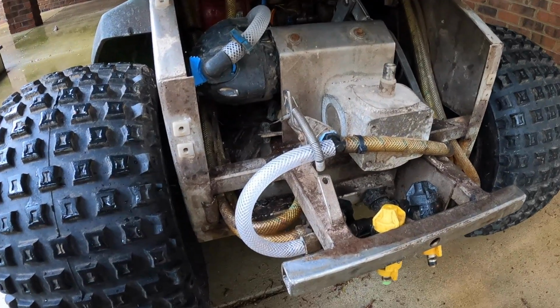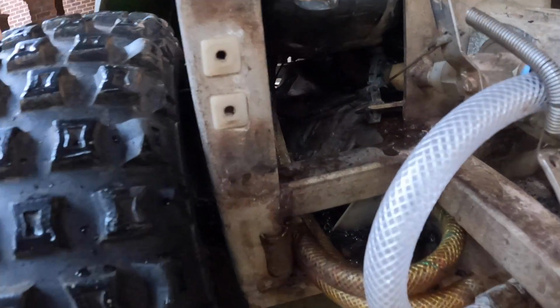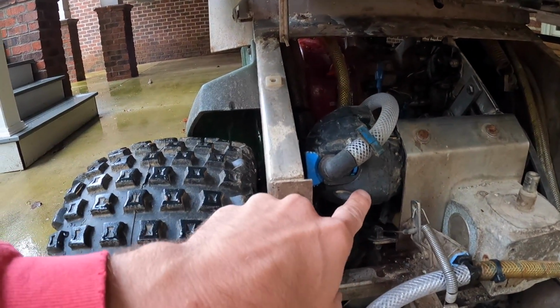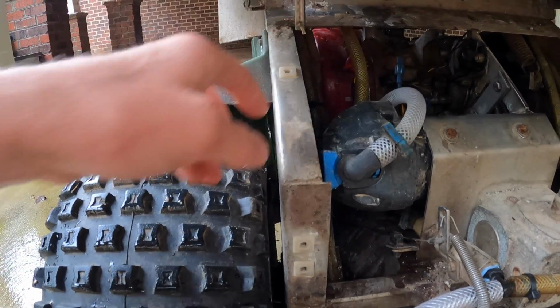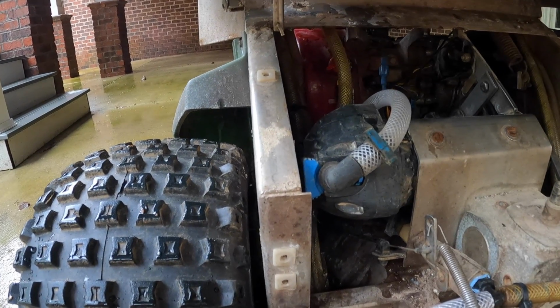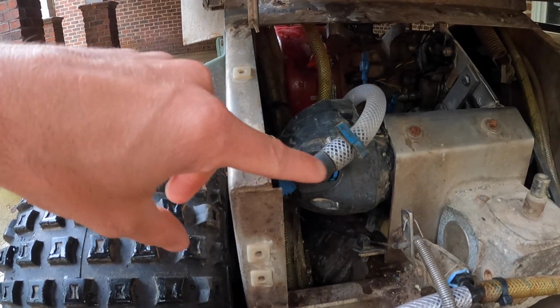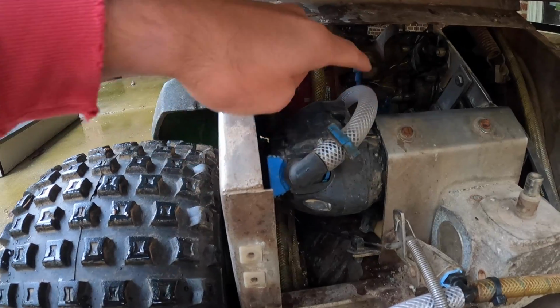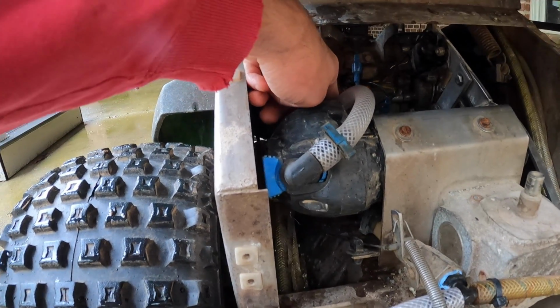So here you can see the setup that I'm running. I've got the suction coming in up under on the back side of the pump where you can't see it. It was originally on this side of the pump, so we shortened up the suction line probably 8 inches, maybe even close to a foot, and then we put the discharge on this side, and then the discharge is going into its normal tee. Nothing changed there.